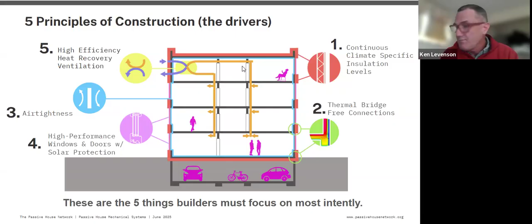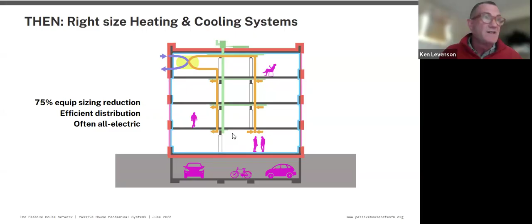With those five things, we've made an efficient building. Then we want to right-size the heating and cooling systems — that's where we're headed. We're often seeing about a 75% size reduction, with more efficient distribution. Because the windows are so good, we typically don't need perimeter heating and cooling; we can pull it back to the core of the building. So our distribution networks can be smaller, and with the lower loads, there's a big opportunity to electrify and simplify.